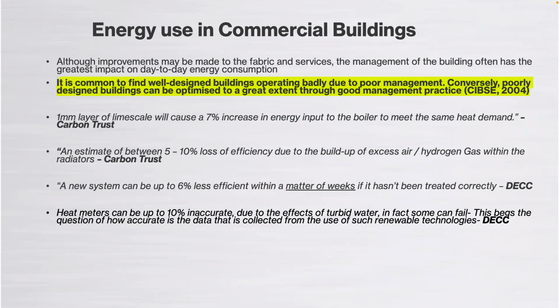Again, some anecdotal examples of what's been out there, but you can essentially lose 6% of energy performance in your system in a matter of a week if it hasn't been treated correctly. If you're in a hard water area, you can lose up to 7% just from really an eggshell layer of scale that might bake on your boiler heat exchanger as well.